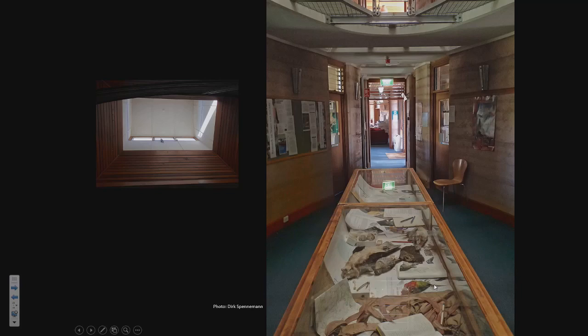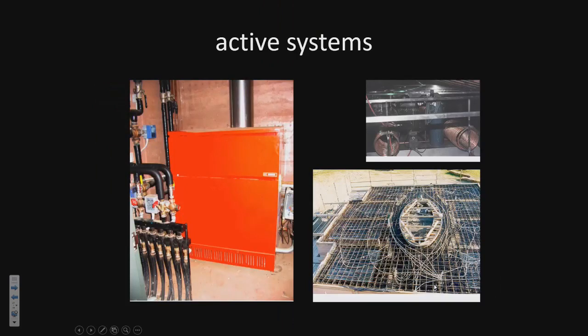They're all non-toxic paints. This is what the hydronics looks like. So that's a slab prepared with the hydronic pipework. There's different zones. Each office, I think they're paired, and then they go to a feeder pipe, and those feeder pipes go back to a manifold, and that can be fed either by the solar tank, and that's the exchange coils with the solar panels to heat the water in the tank, or to cool it for night cooling in the summertime. We'll take from the tank if the temperatures are sufficient, and if they're not, this boiler will kick in. So that is the plant room for an office building for over 100 people. Except there's 2 of those, sorry.